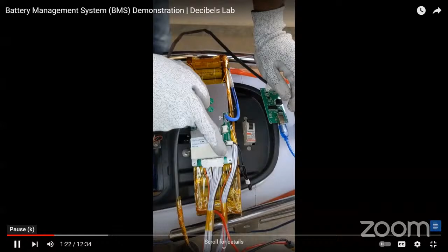Then the main wiring comes here, which connects all the series of the battery module. It starts from the negative wire, known as BC0, the black wire, which directly connects to the negative terminal. In total we have 14 wires, of which 12 are white, one is negative, and one is positive, which is in red color. So first you connect to the negative terminal, then in continuation you connect all the white wires, which you can see have already been connected here and here. Then at last you connect the red wire to the positive terminal. So this is how the wiring connection is.